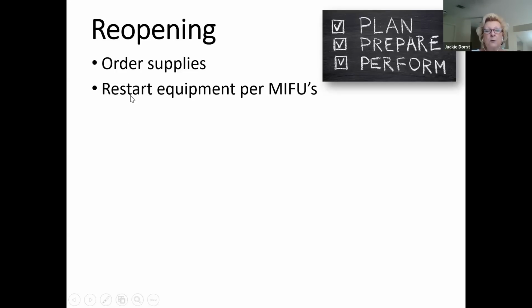We also need to look at how to restart equipment that's been idle for 6 to 12 weeks before getting started—your vacuum pump, your compressor may have been shut down during this time. So you need the manufacturer's instructions for use, the MIFUs, for how to restart all the equipment. Your autoclave, your sterilizer, you're going to have to clean it.